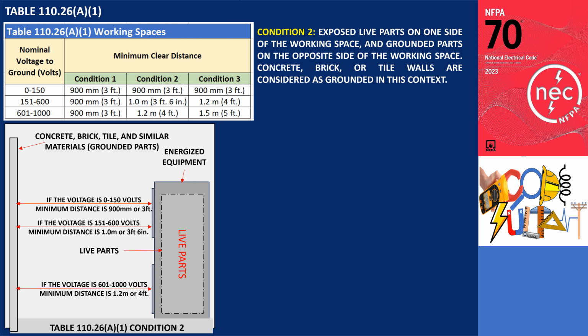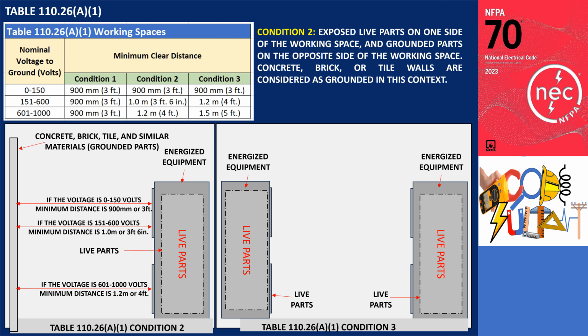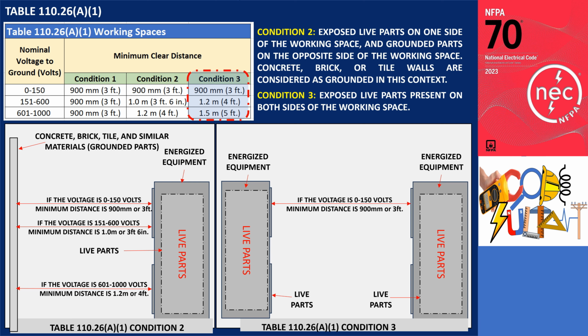When exposed live parts are present on both sides of the working space, condition 3 is applicable. For this condition and when the voltages range from 0 to 150 volts, the minimum required clearance distance remains at 900 millimeters or 3 feet. When the voltages fall between 151 and 600 volts, the required distance increases to 1.2 meters or 4 feet. For voltages ranging from 601 to 1000 volts, the minimum required clearance distance is 1.5 meters or 5 feet.